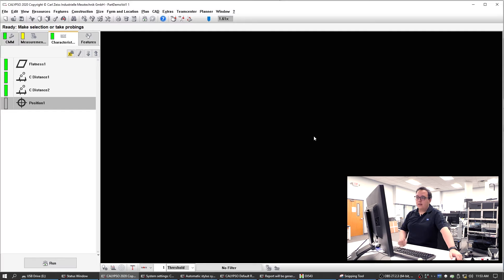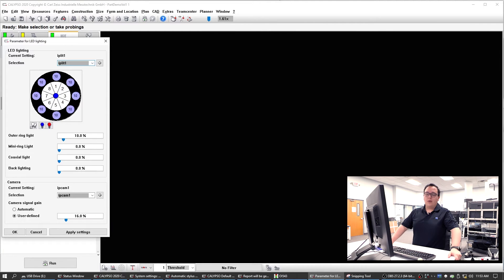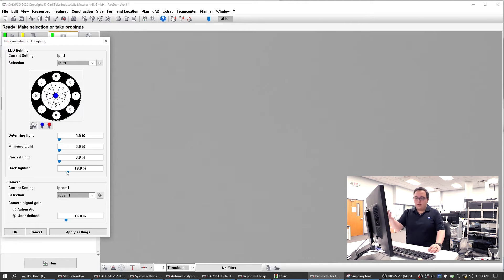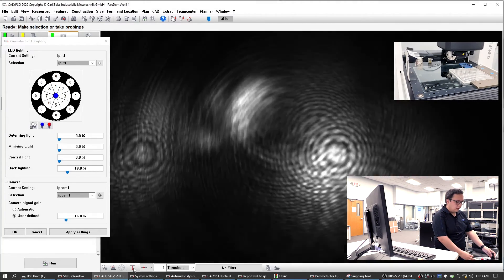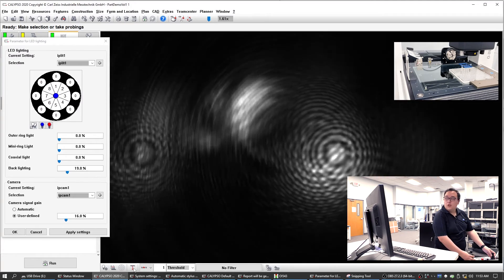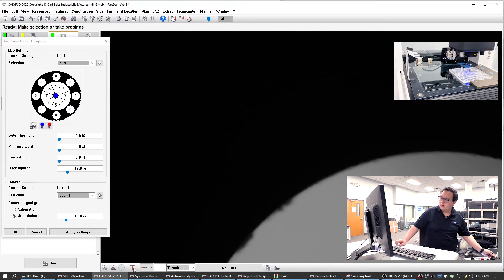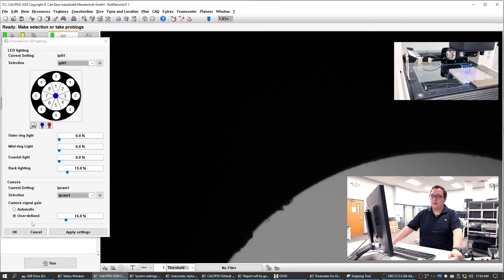What it does is turn on the camera and the top light. We want to actually make sure that the light comes from the bottom — we don't need it reflecting, we need it transmitting. So we need backlight. We can see that we're getting some color from here. Once we turn on the camera, we actually have this little laser that tells us where the center of the objective is pointing. So let's go ahead and move that to where the hole is — I want to make sure that I have the right light setting when we're actually going to be measuring this. Oh, and we can also tell that it's a little dirty — there's maybe some flashing here, maybe some dust. We're going to use backlighting — 19% seems like a good value.